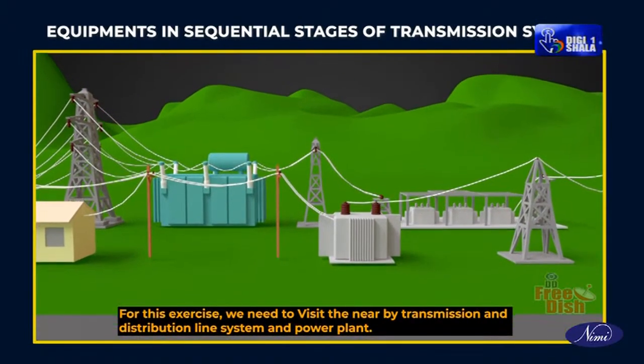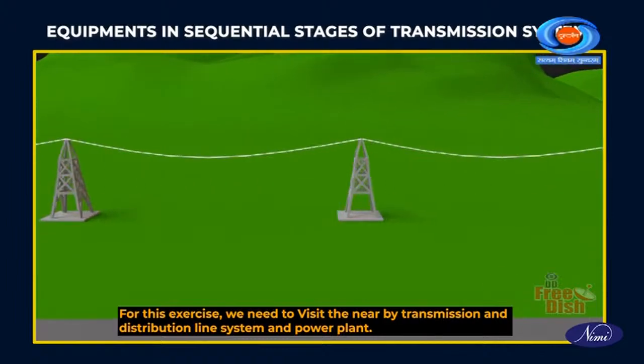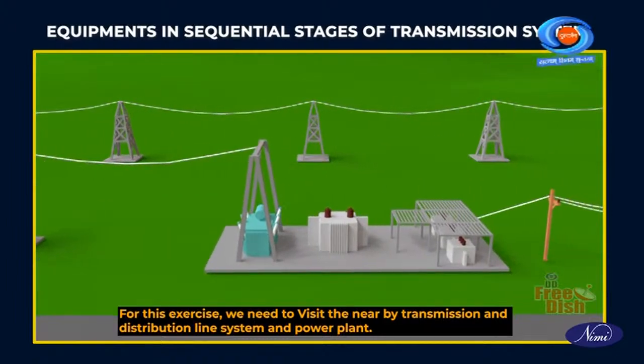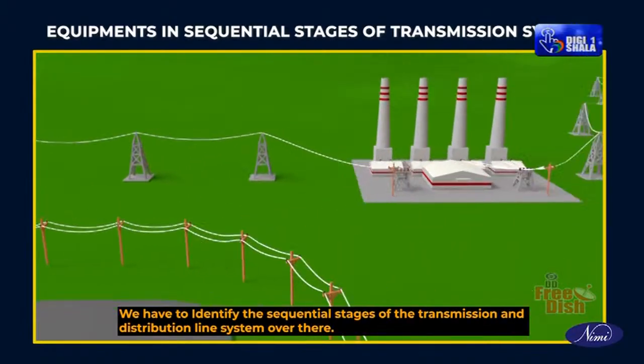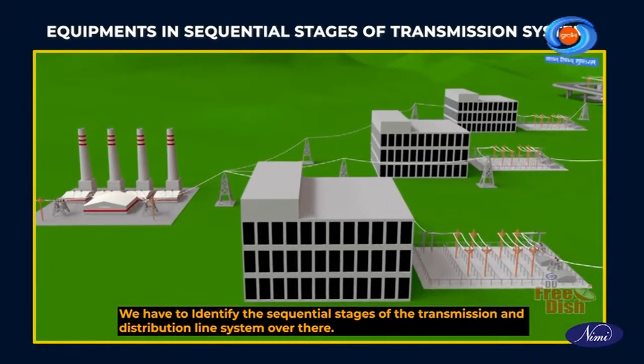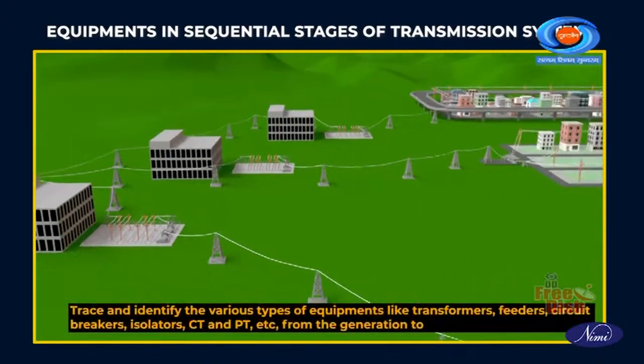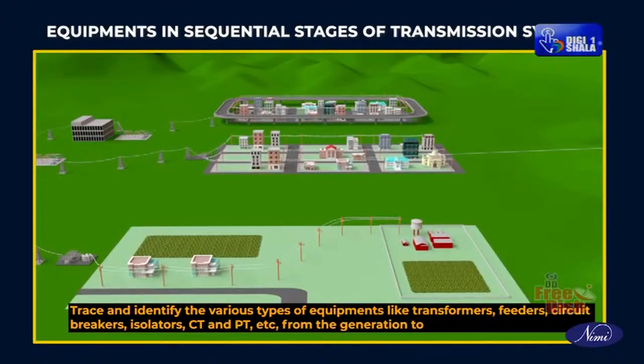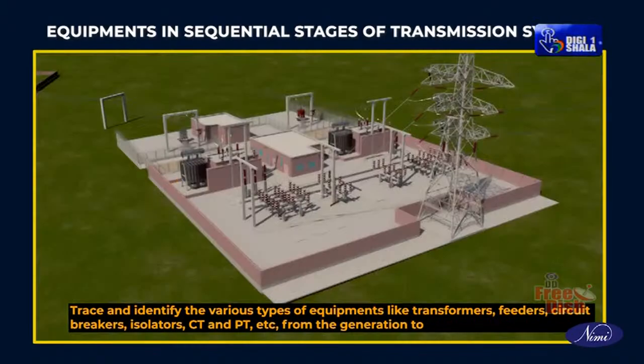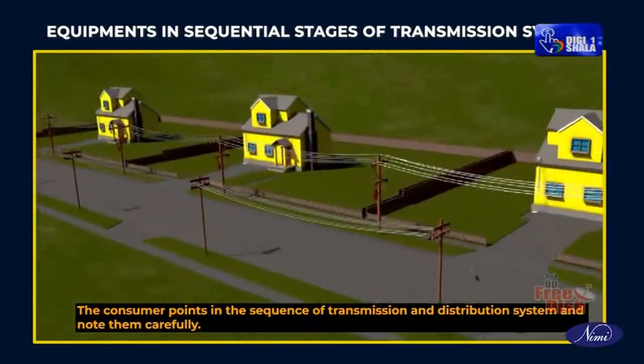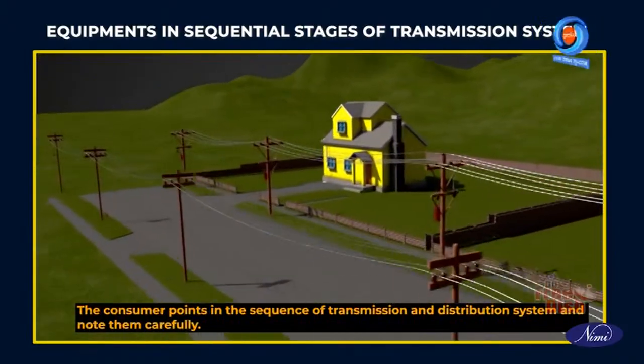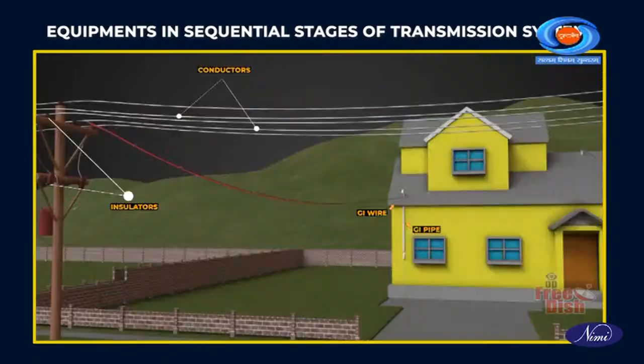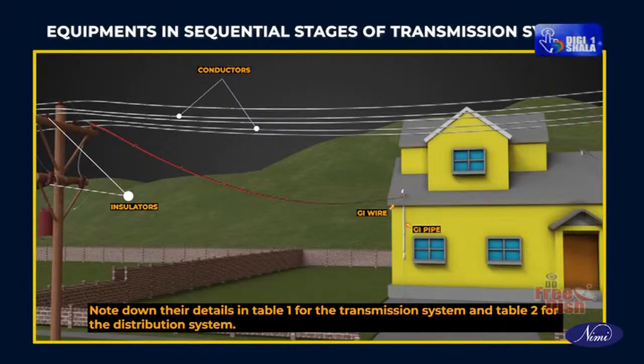For this exercise, we need to visit the nearby transmission and distribution line system and power plant. We have to identify the sequential stages of transmission and distribution line system over there. Trace and identify the various types of equipments like transformers, feeders, circuit breakers, isolators, CT and PT, etc. from the generation to the consumer points in the sequence of transmission and distribution system and note them carefully. Note down their details in Table 1 for the transmission system and Table 2 for the distribution system.